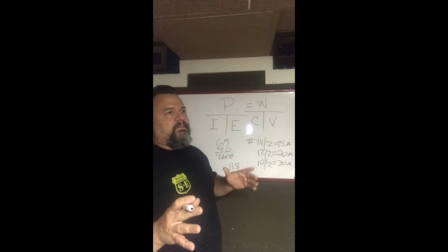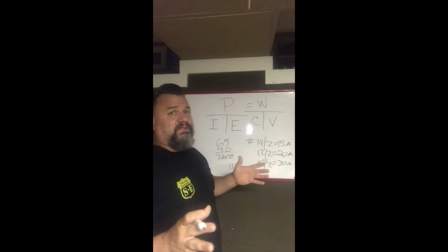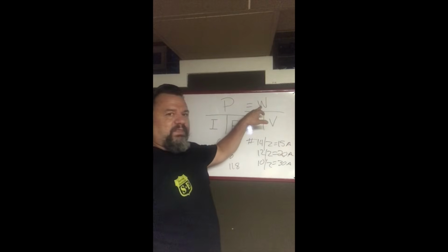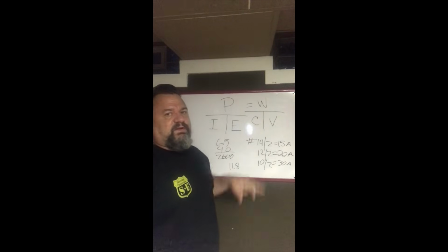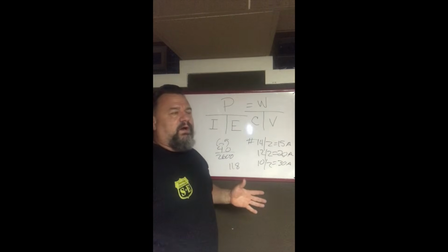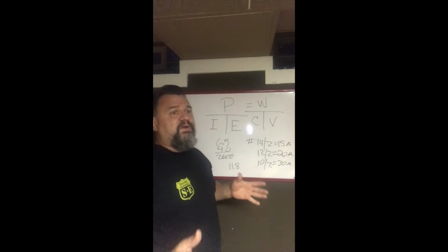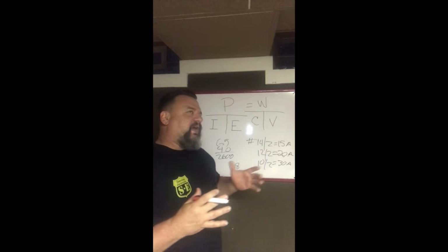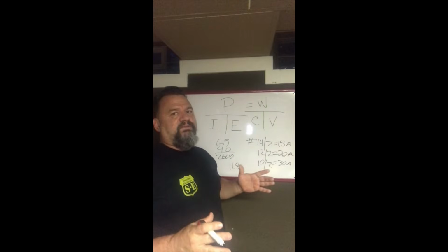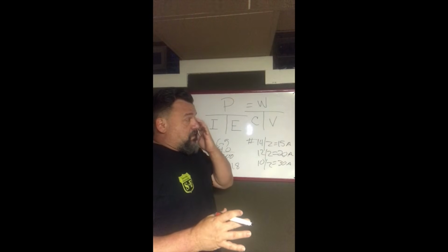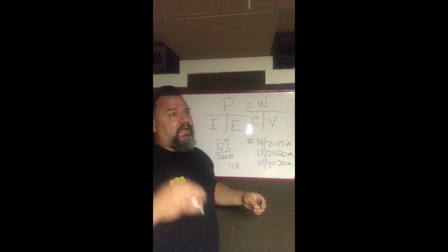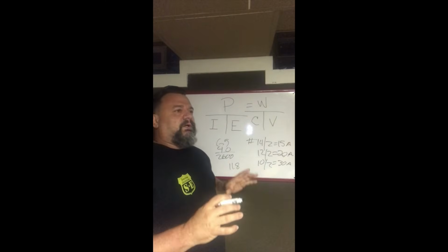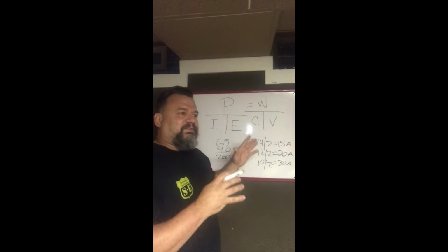Now as far as your plugs go, I make it a habit to put maybe two small bedrooms on a circuit. We don't have a determined wattage for our bedroom. We don't know what's going to go in there: curling irons, blow dryers, computer, we have no idea. So you have to make an educated guess. For me, it's about 10 to 12 devices on a circuit. So I do two small rooms on it, and each one of the switches is considered one, because that switch doesn't draw anything, the light does. So that's how I do one 15 amp circuit.